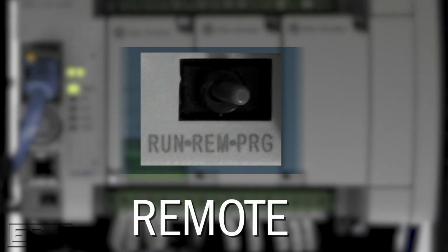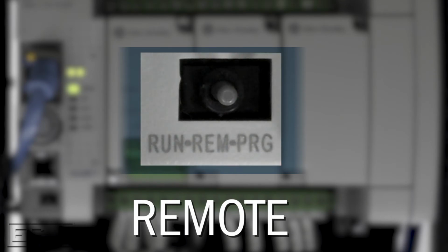The third position, and the most common, is remote, which means the mode can be changed from the software to remote program for downloading purposes or remote run, which allows the logic to execute and online editing.